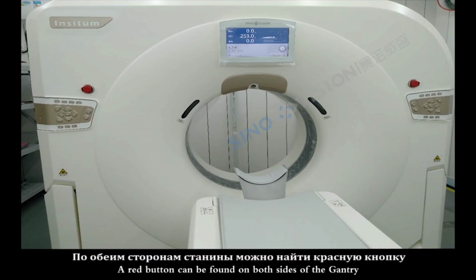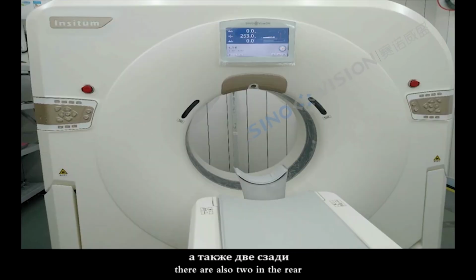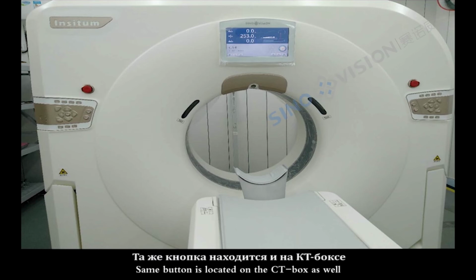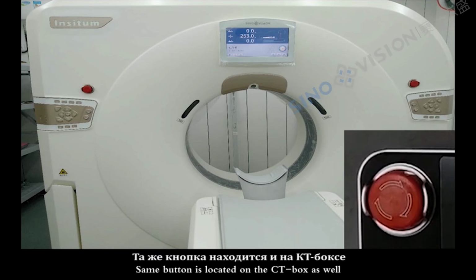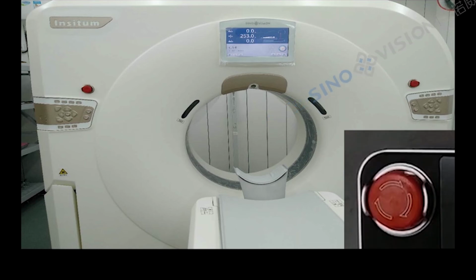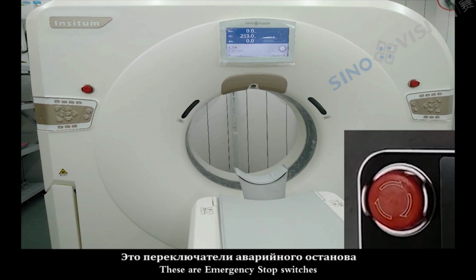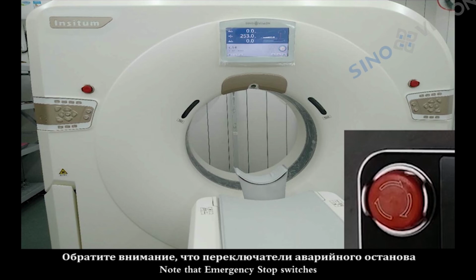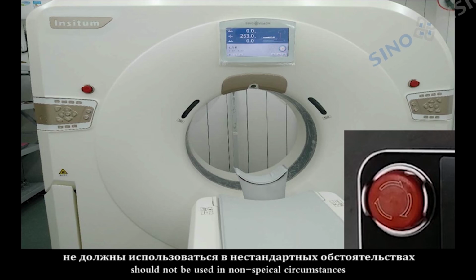A red button can be found on both sides of the gantry. There are also two in the rear. Same button is located on the CT box as well. These are emergency stop switches. Note that emergency stop switches should not be used in non-special circumstances.